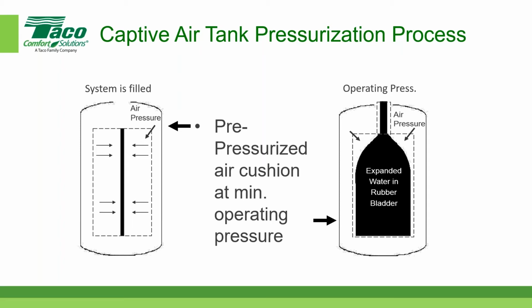Anything to add to that, Rich? I would say the same thing. In fact, the majority of bladders I've seen have not had material deterioration over time. Usually there's a tear in the bladder for one reason or another, something sharp inside the tank that was unanticipated. It's pretty rare to see a bladder fail. They last a very long time with very, very few failures over their life expectancy. And by the way, I've seen folks replace a whole tank instead of a bladder in the field just because of the cost difference.